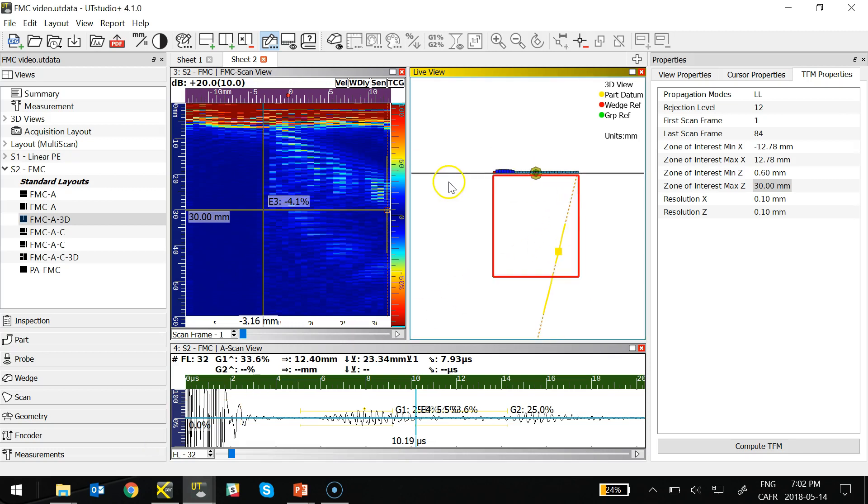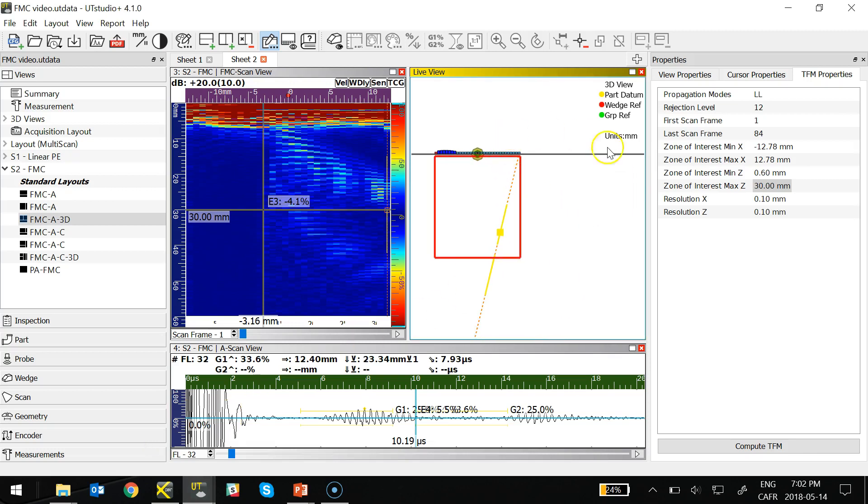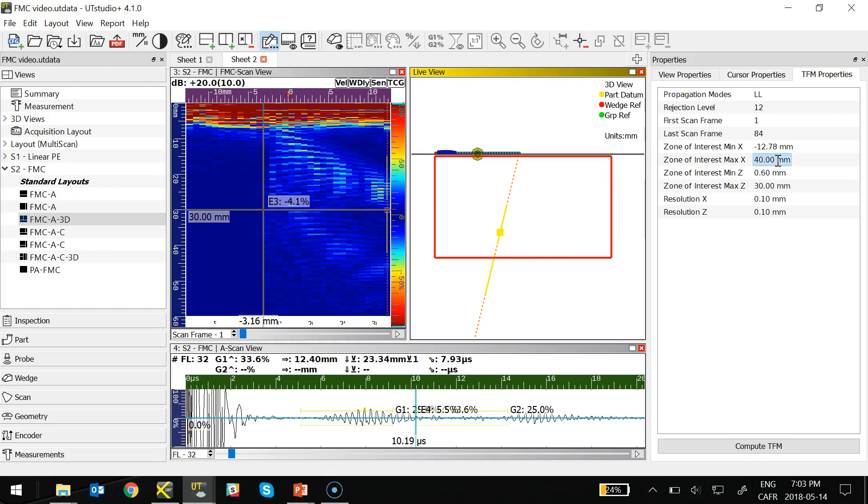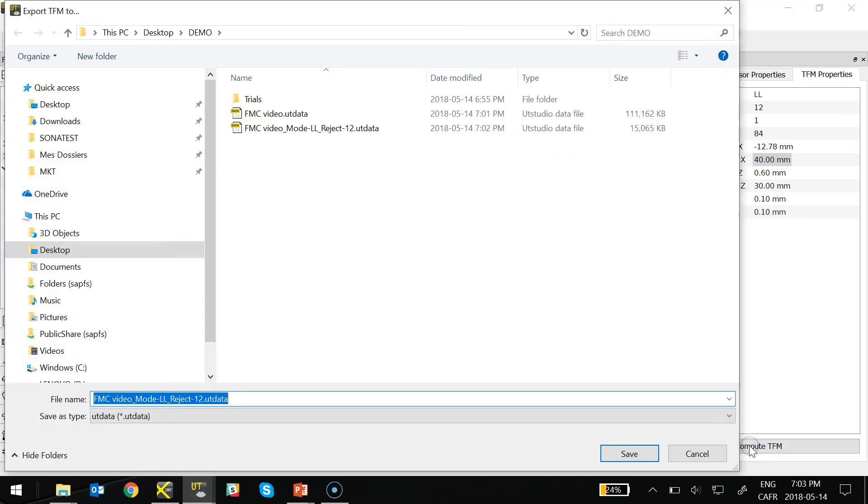Now, to show all the advantages of recording the FMC scan and then recomputing TFM images post-acquisition, I'm going to extend the box, or the TFM analysis box, to include all the SDHs that were on my calibration demonstration block.